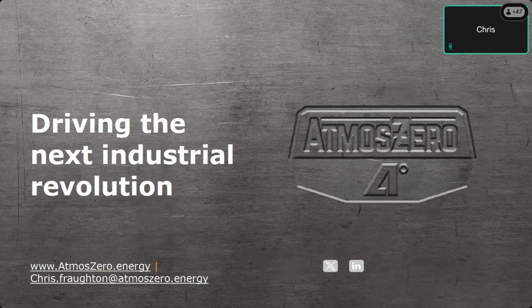Great. So we have time for a few more questions. Does it carry limitation on inlet water temperature or delta T supply and return? It does not, because we are really managing that through the glycol loop. However, if you on your facility side have a tight specification on what that delta T should be, we can also vary our glycol loop accordingly. It's something that we need to scope out and discuss early on in a project.